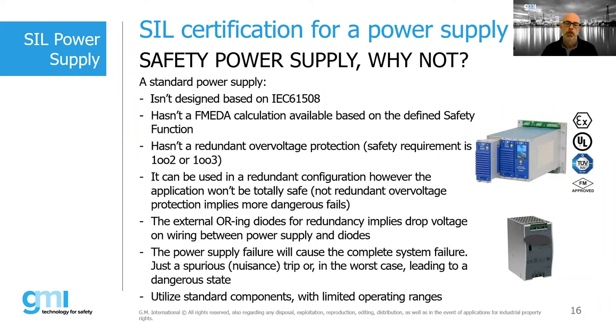In addition, a standard power supply has a higher number of spurious faults than a separate power supply. We know well how a spurious fault can also lead to dangerous failures for the application. And also, standard power supplies use internal components with limited operating range. This affects the lifetime of the device. For this reason, internally to the safety power supply, components with a higher operating range are used that allow the system to work at a lower stress level. This leads to fewer failures and consequently a considerably longer life than a standard power supply system.